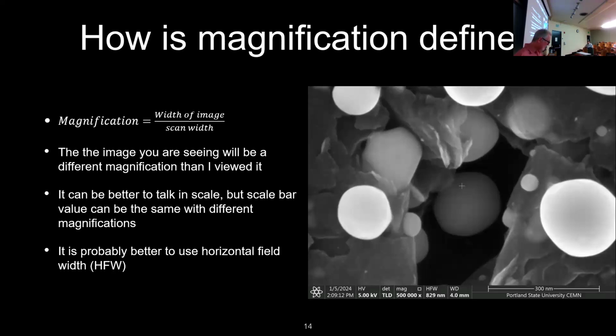We cannot use that mode with ferromagnetic samples, as the lens becomes a very high power magnet, and it will tend to suck your sample into the lens, destroying it. And that has happened in this lab, not on this microscope, on another microscope, but that has happened. And it's very expensive. It makes me sad when it happens.